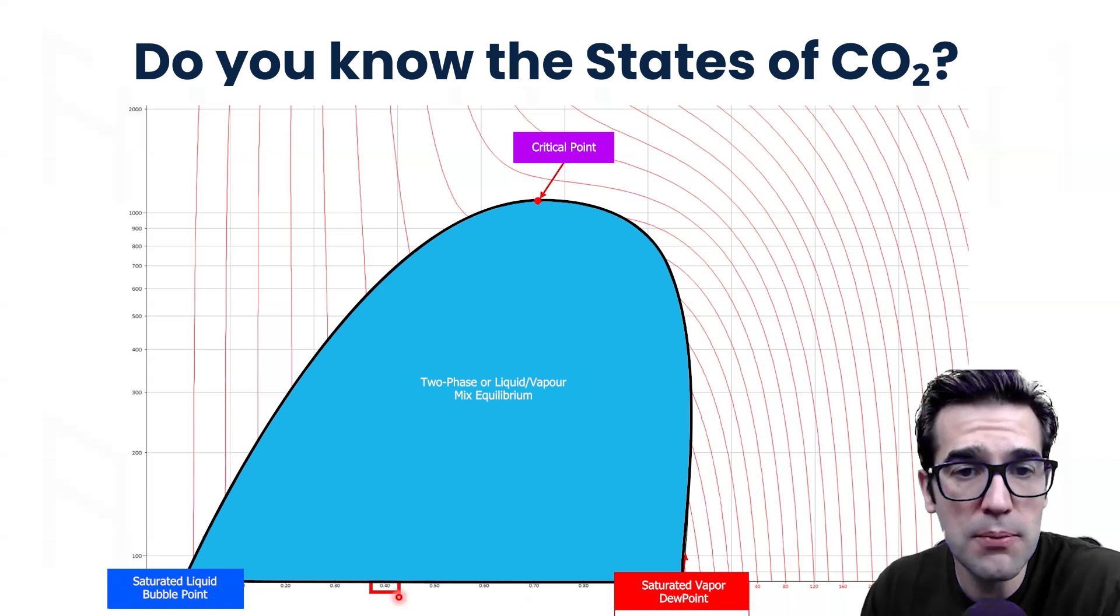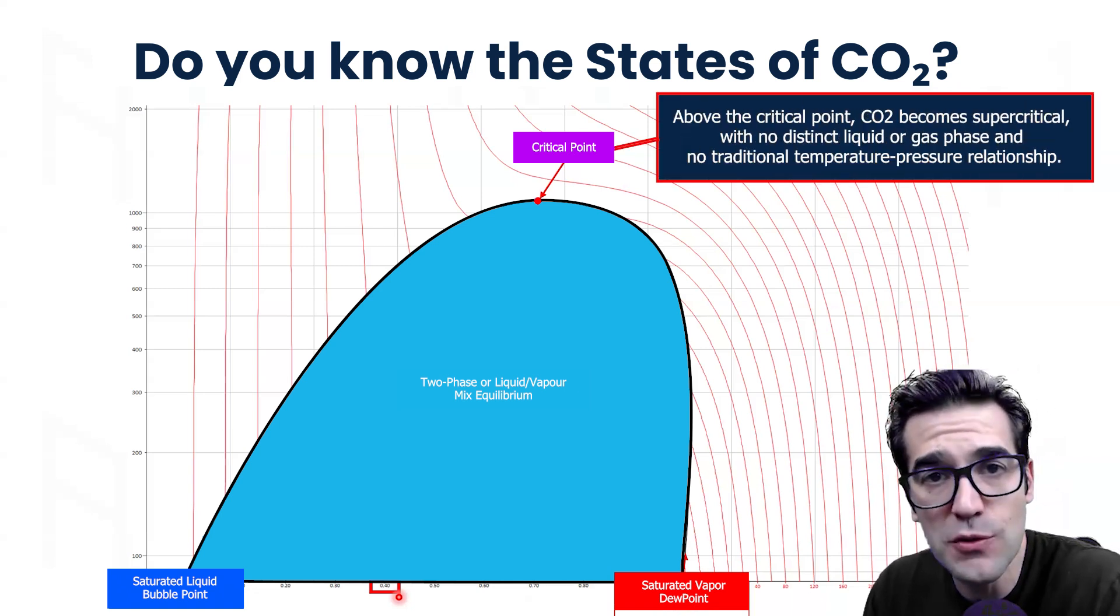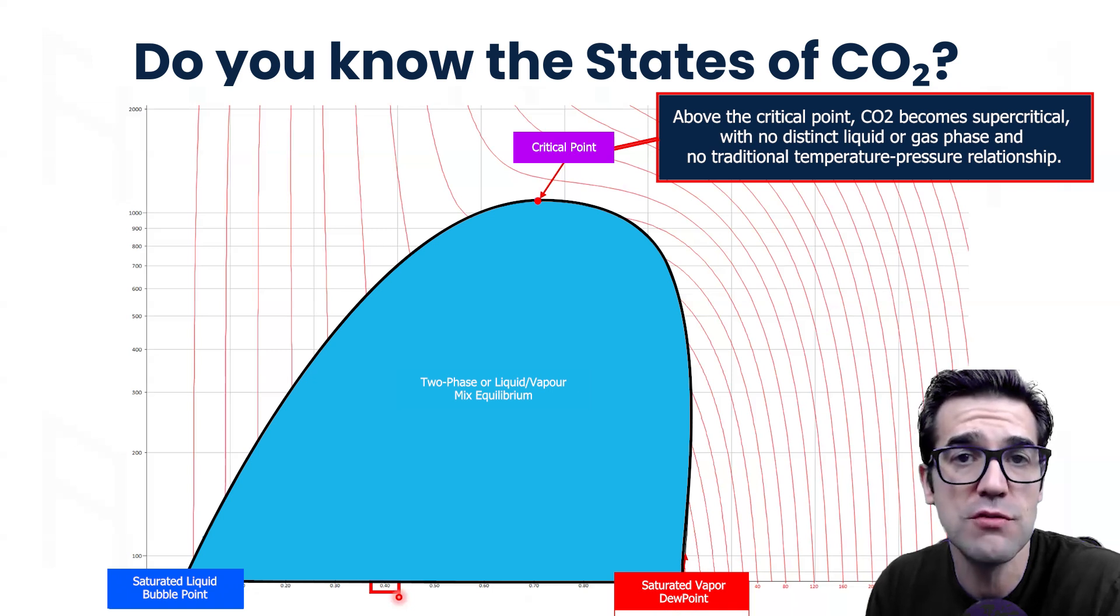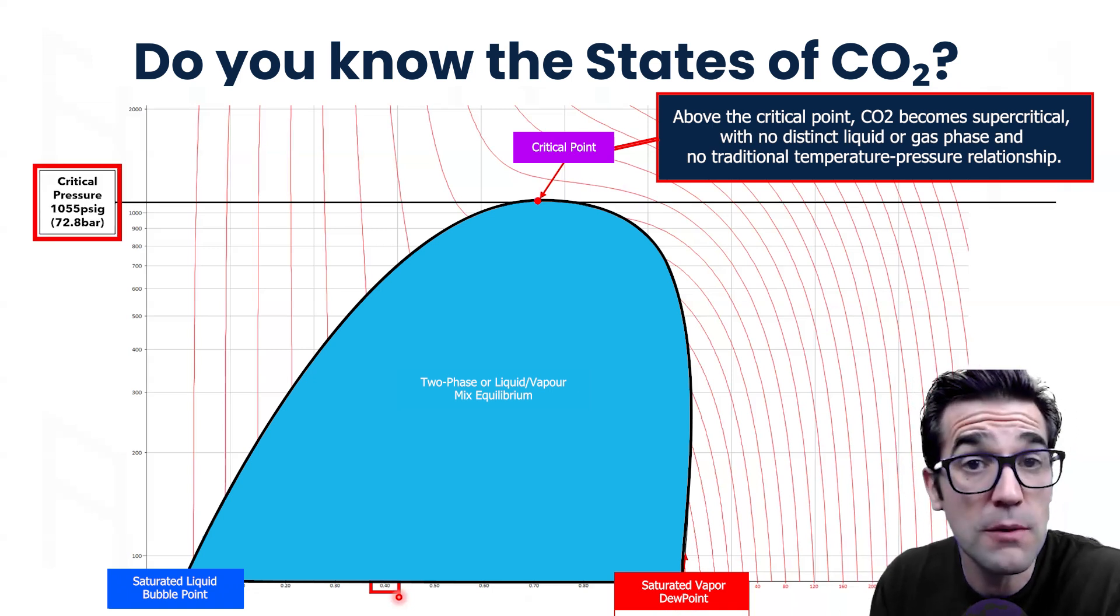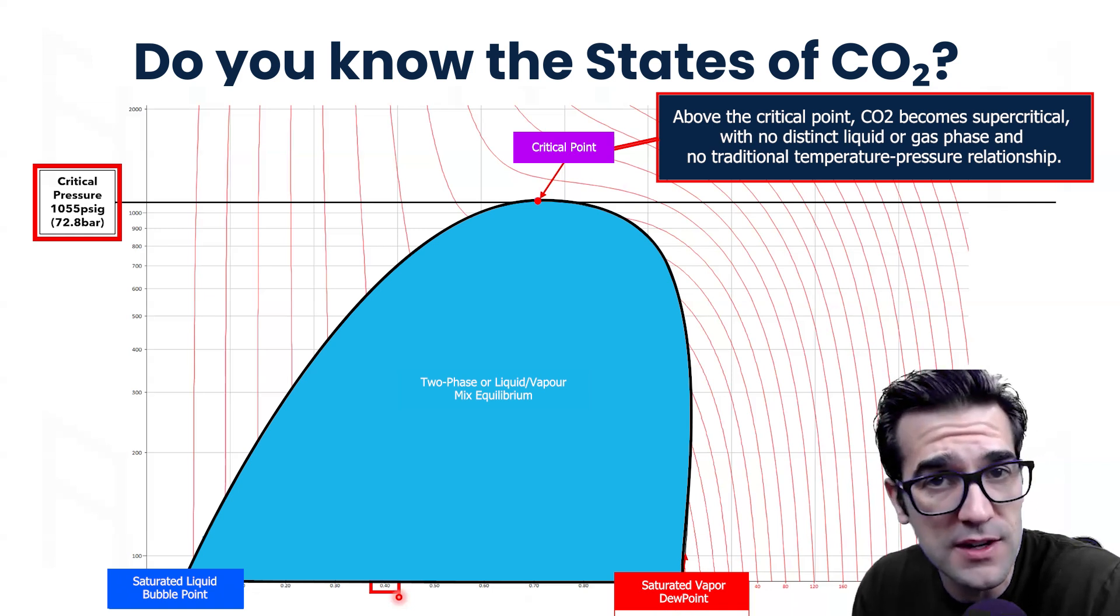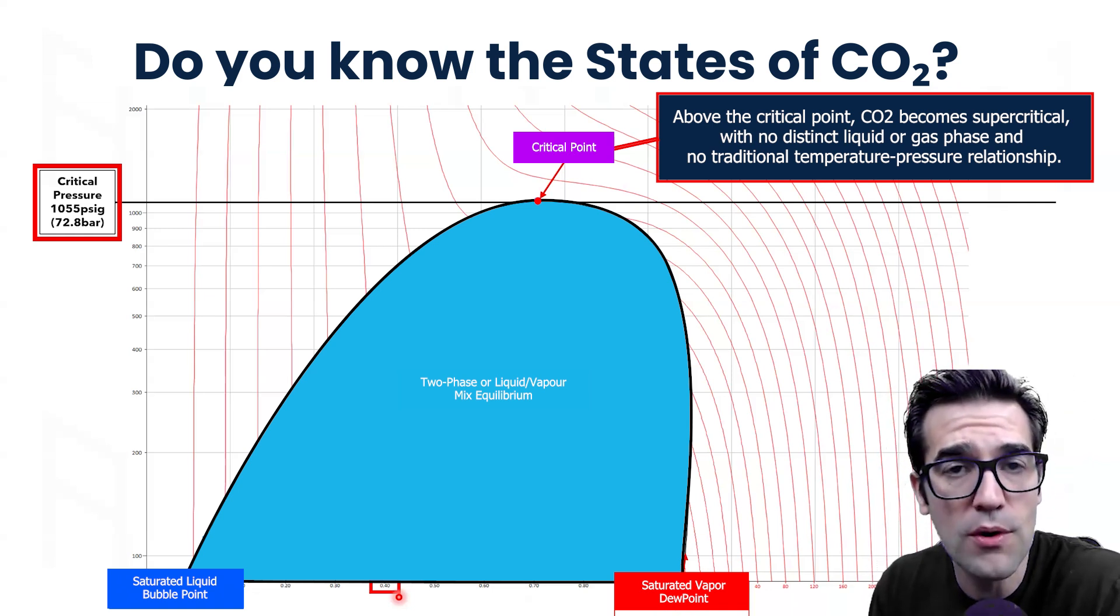Next point is the critical point. Anything above the critical point is an undefined fluid. There's no pressure temperature relationship. How do we find the critical point? First step is the critical pressure. The critical pressure is 1055 PSIG or 72.8 bar. This is very important to know.